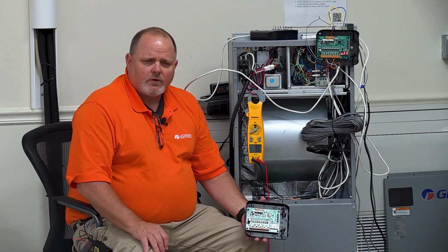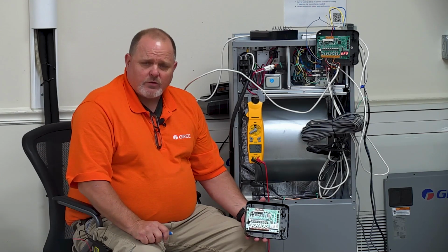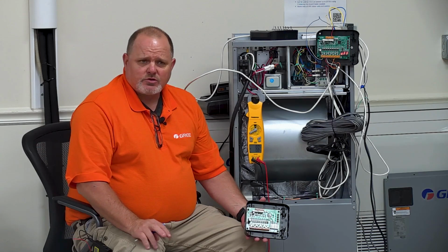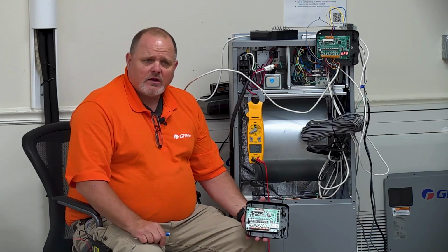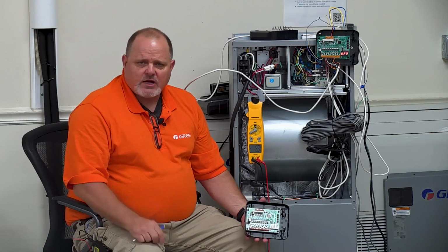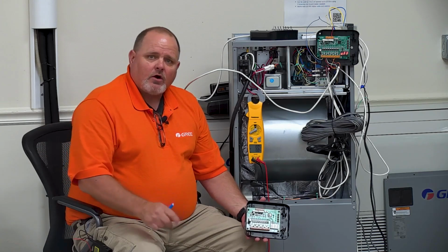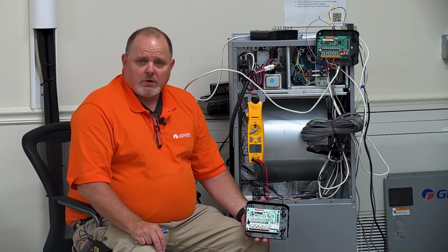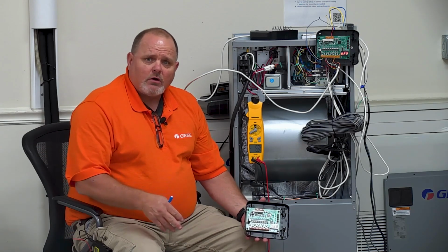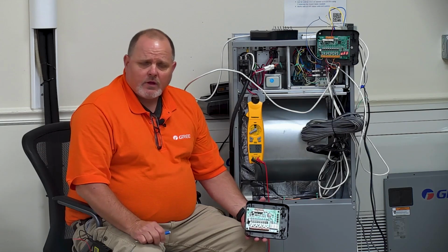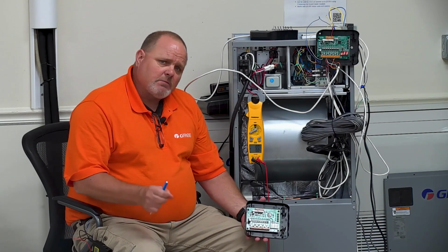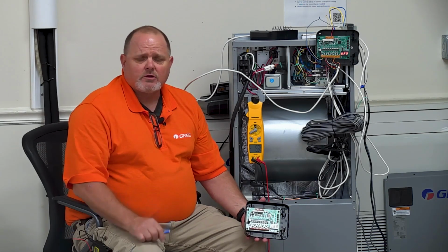Before, with the 24-volt adapter, when you got it, it was very simple. You used a standard heat-cool thermostat, not a heat pump thermostat. And when you got a Y call, it would run the unit in cooling mode. And when you got a W call, it would run the unit in heat mode. So this is going to be a little different. This is going to be more like what most of you are probably used to.